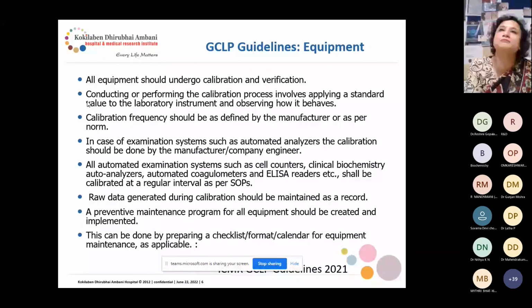But when I was checking one instrument, the raw data were not available. It was done long back, maybe 10 years back, but I can't find the raw data because it was not archived properly. So these are the common deficiencies we see in terms of calibration. Whenever calibration is done by the lab or by the IVD people or the engineer, the raw data should be maintained in that calibration file.